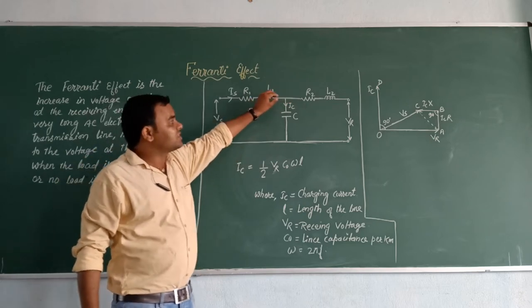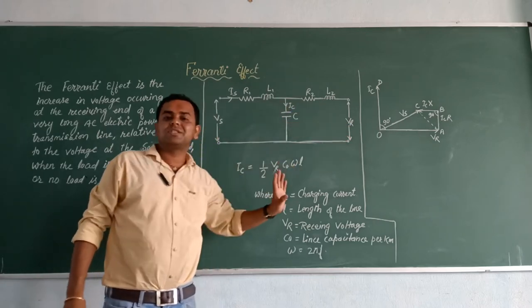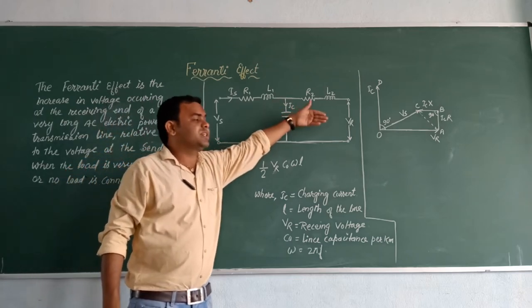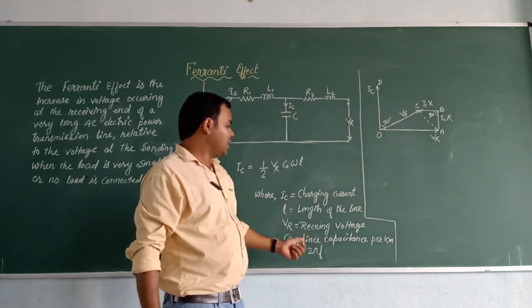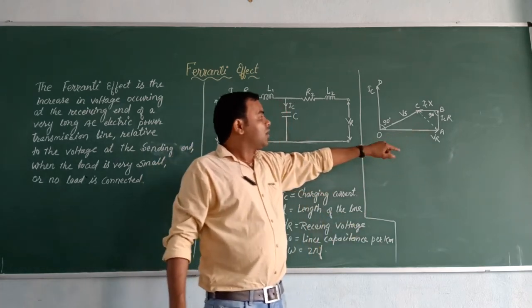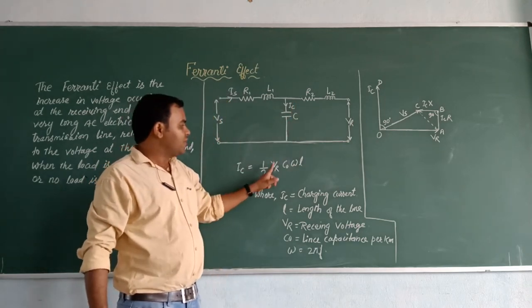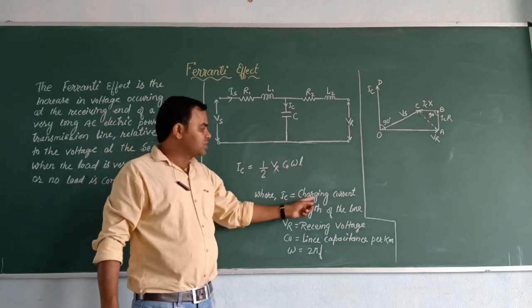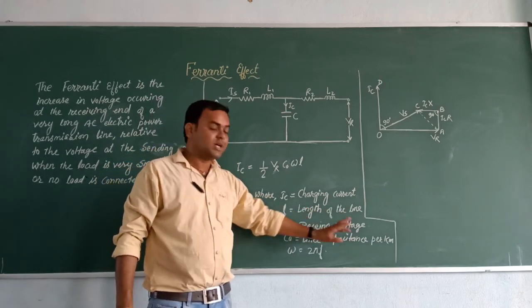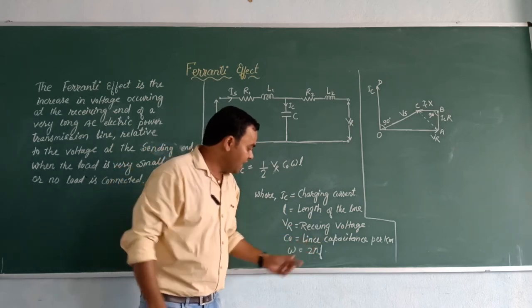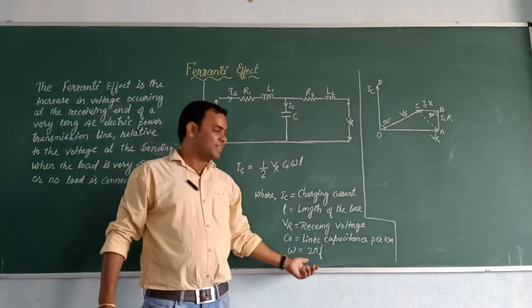The receiving end voltage will increase and the capacitive property is uniformly distributed and the voltage is added. VR is the receiving end voltage and the IC current is the charging current. What is the value? IC = 1/2 * VR * C0 * omega * L, where IC is charging current, L is length of the line, VR is receiving voltage, C0 is line capacitance per km, and omega is the frequency.